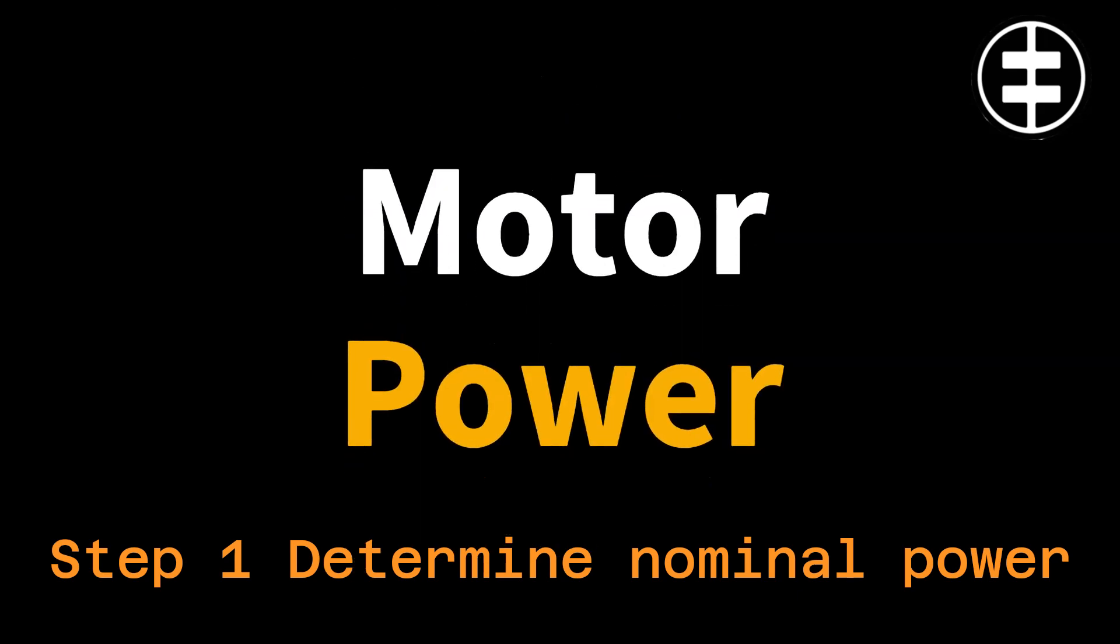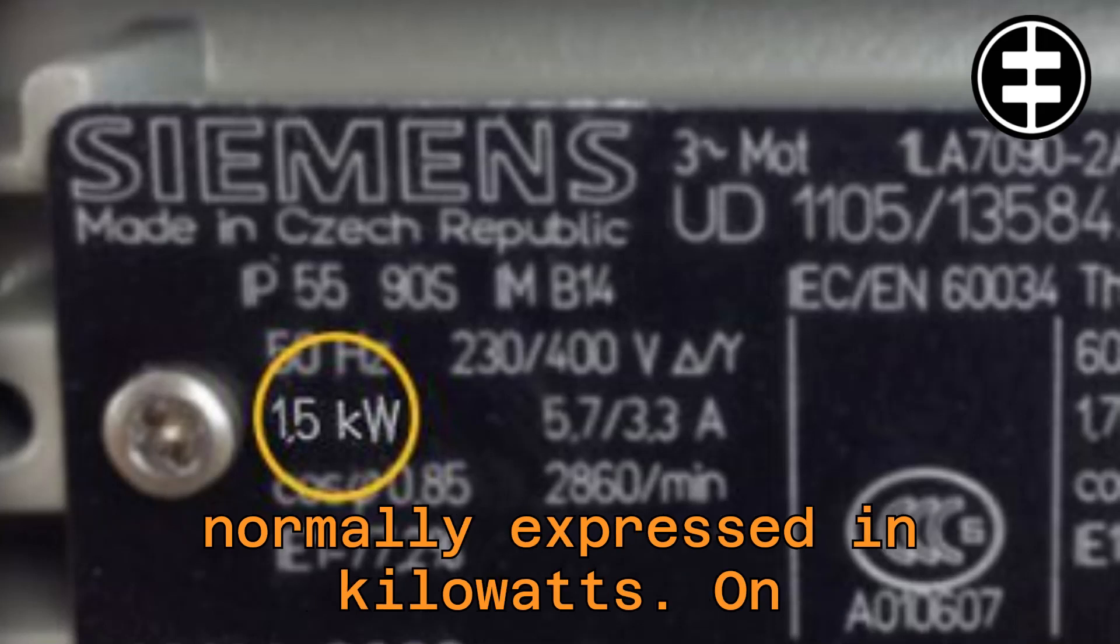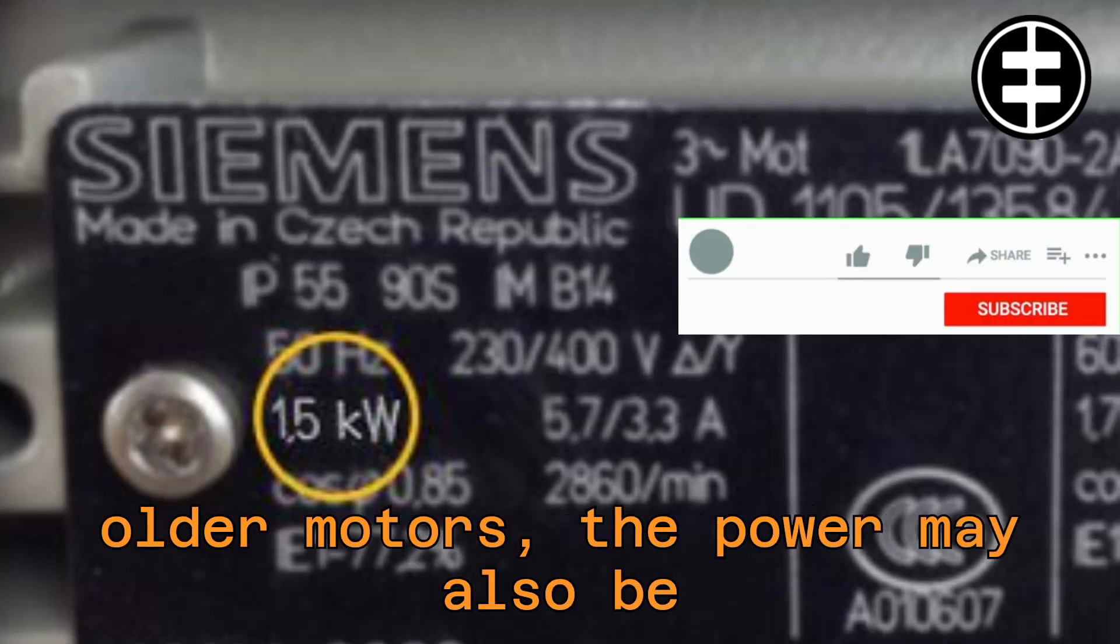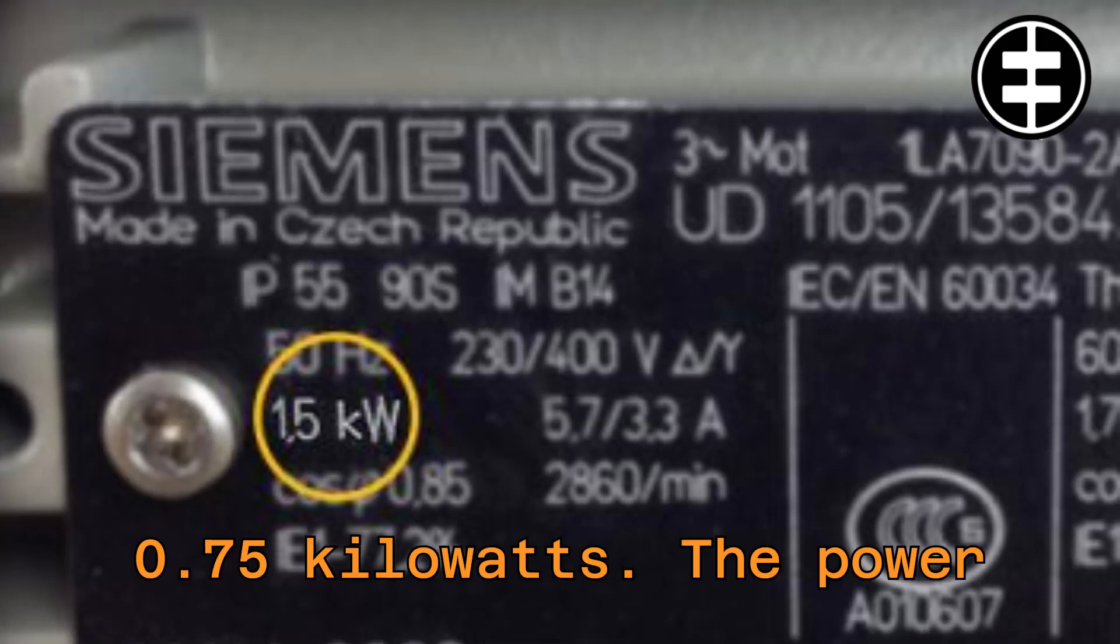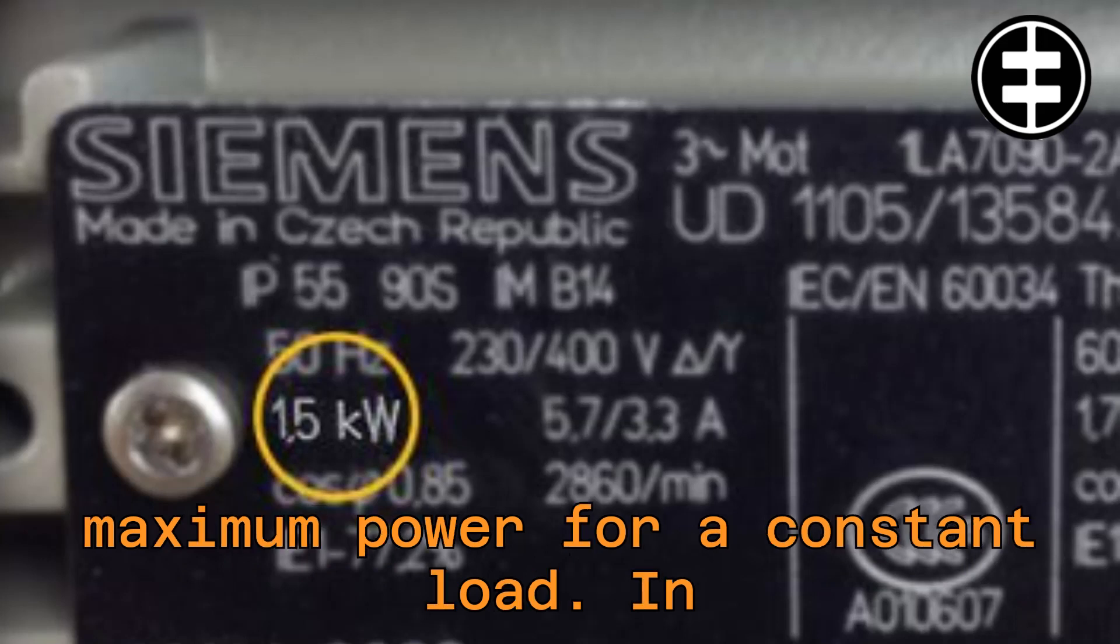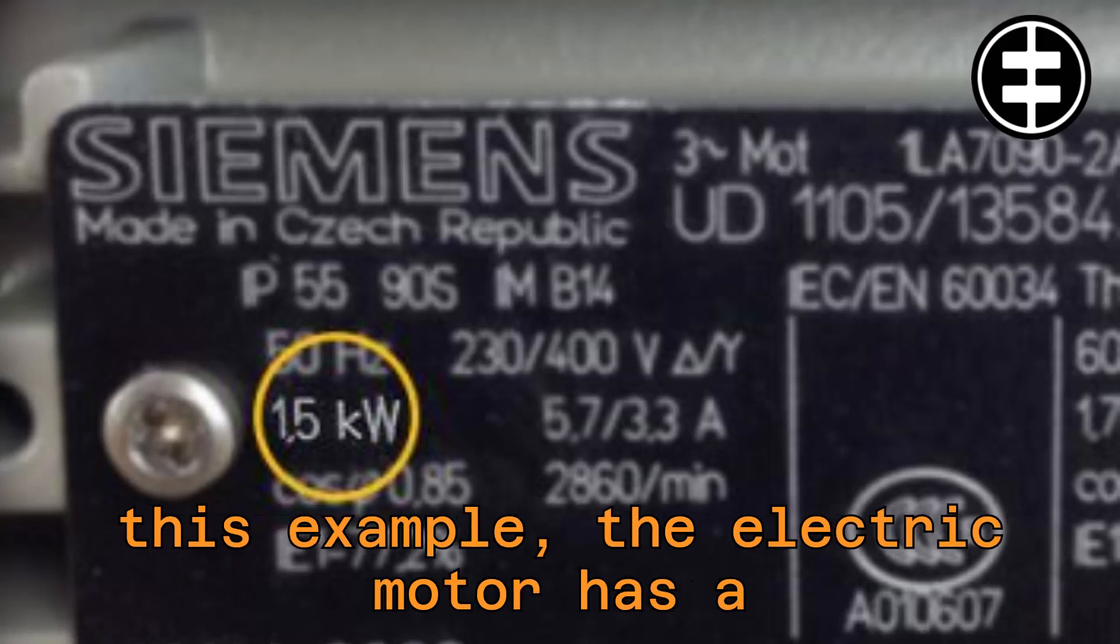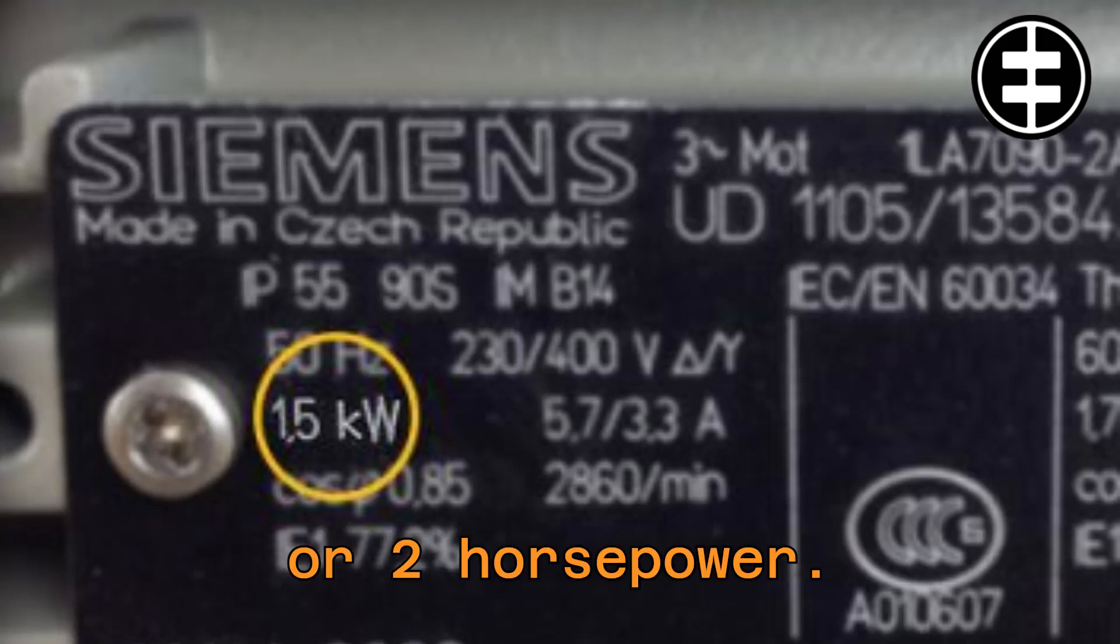Step 1. Determine nominal power. The nominal power of an electric motor is normally expressed in kilowatts. On older motors, the power may also be expressed in horsepower. The conversion is 1 horsepower equals 0.75 kilowatts. The power of an electric motor is based on the maximum power for a constant load. In this example, the electric motor has a nominal power of 1.5 kilowatts, or 2 horsepower.